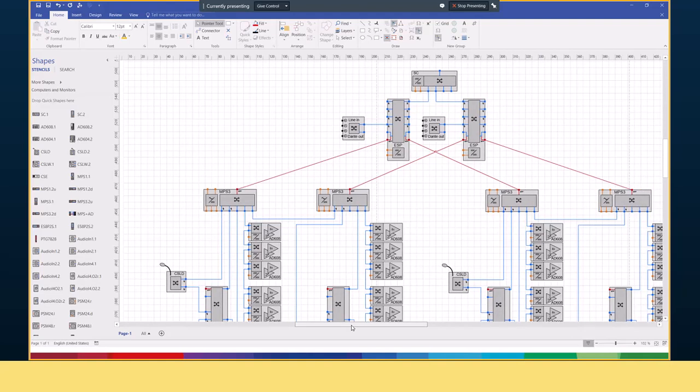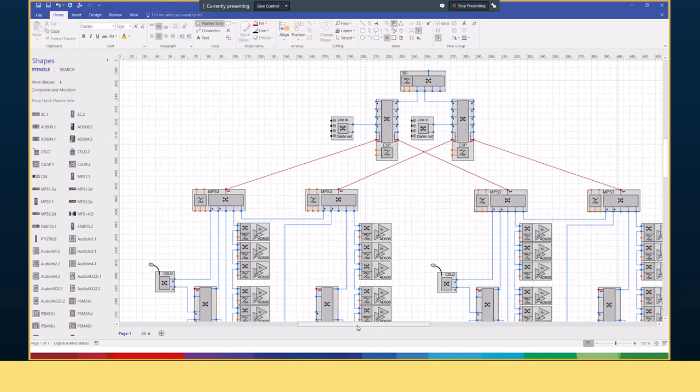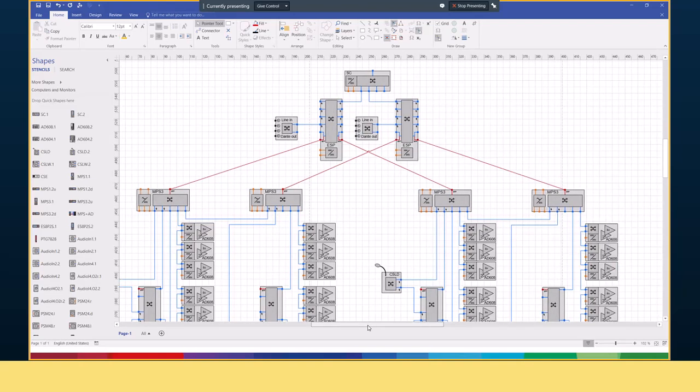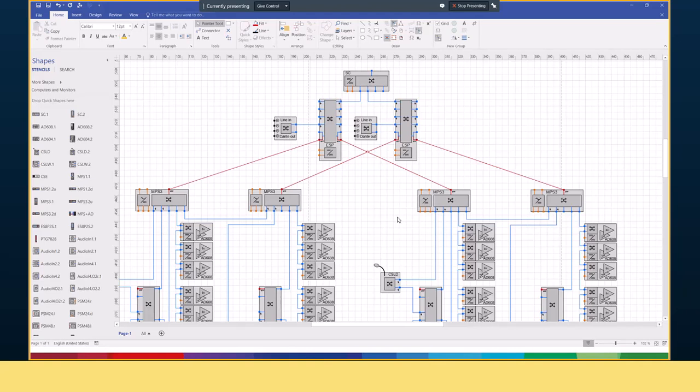Another thing is, if you look at this diagram, the central system, and the two systems on the left and the right are remote, you immediately see that there is no power here. Yeah, so you have to solve that. In a diagram like this, you see that immediately. So what I do, I will just take, I'm not sure if I have to use this one. Yeah, I can use an MPS as the power supply. I have to do that for the controller.